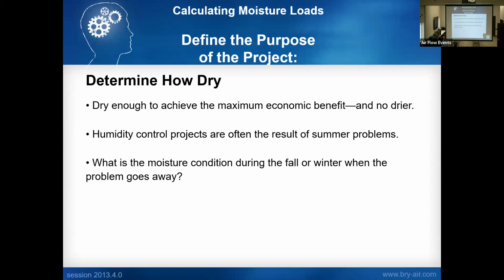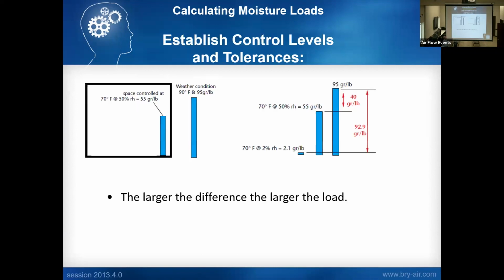And also understanding when the problem occurs. A lot of humidity problems go away in the fall and winter, and we see that a lot. So understanding with the customer when they have the humidity problem, and when they don't, also helps tell us where we need to be as far as design conditions. Again, understanding where you want to be, how dry you want to be. If you've got outside air, you need to be 50% RH, 2% RH. Again, larger the difference, larger the load, larger the cost, more energy.